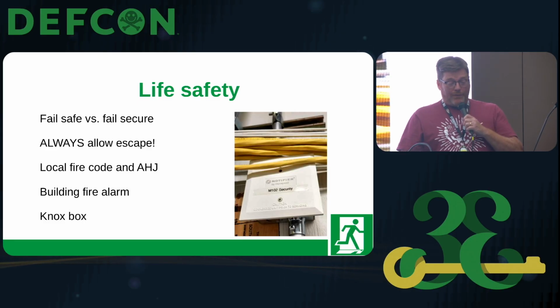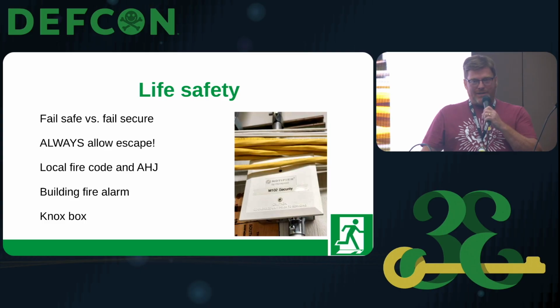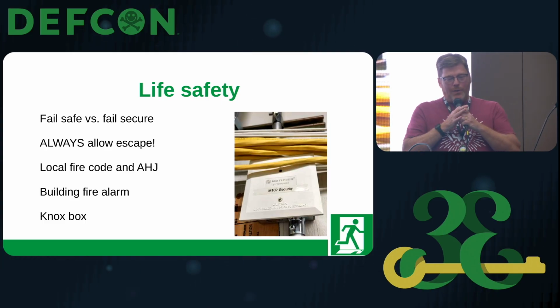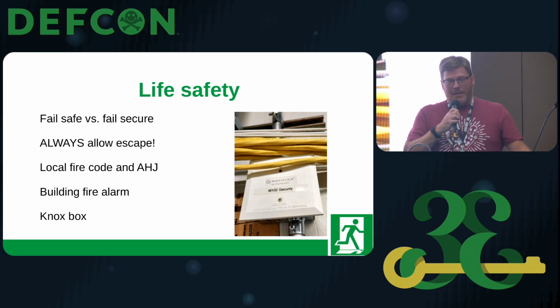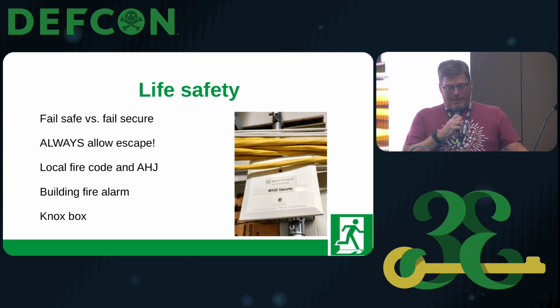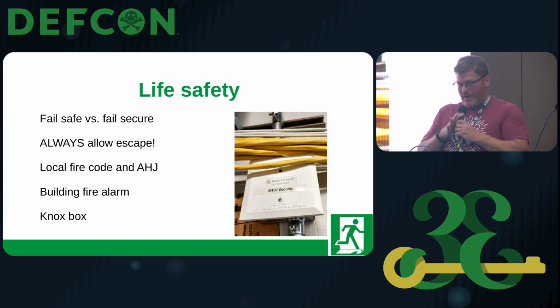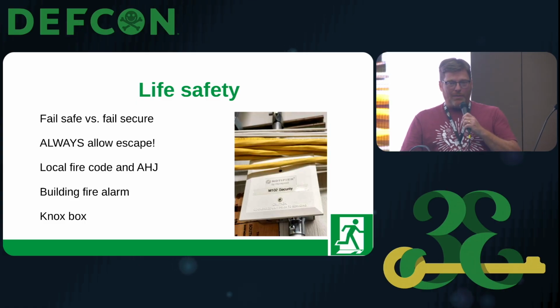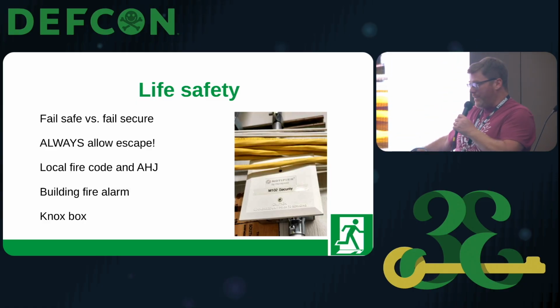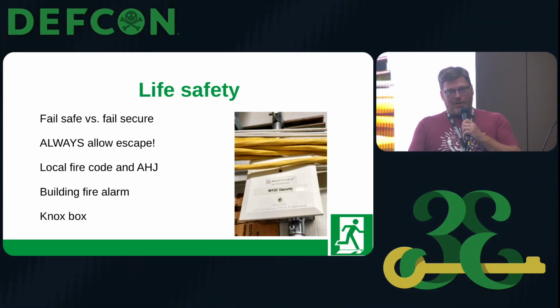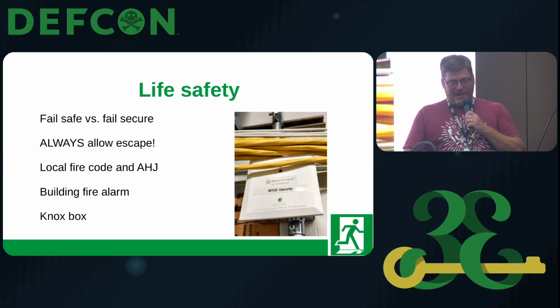Coordinate with your local fire code and your authority having jurisdiction. In some areas that's a fire marshal, sometimes it's a building inspector, but make sure that you have a way for people to escape if there's an emergency. If you are in a high-rise building, you'll have a building fire alarm, and usually part of your lease and probably part of the fire code is that you connect your system using these relays so that if the fire alarm goes off, it automatically unlocks doors so that people can escape.